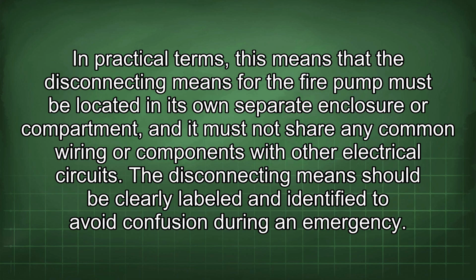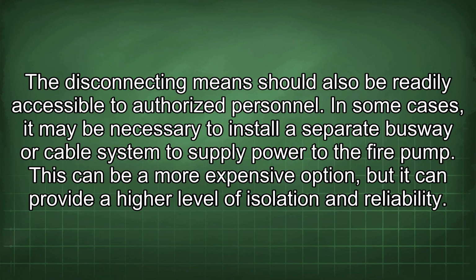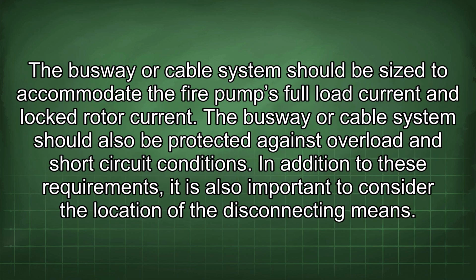The disconnecting means should be clearly labeled and identified to avoid confusion during an emergency. The disconnecting means should also be readily accessible to authorized personnel. In some cases, it may be necessary to install a separate busway or cable system to supply power to the fire pump. This can be a more expensive option, but it can provide a higher level of isolation and reliability. The busway or cable system should be sized to accommodate the fire pump's full load current and locked rotor current. The busway or cable system should also be protected against overload and short-circuit conditions.